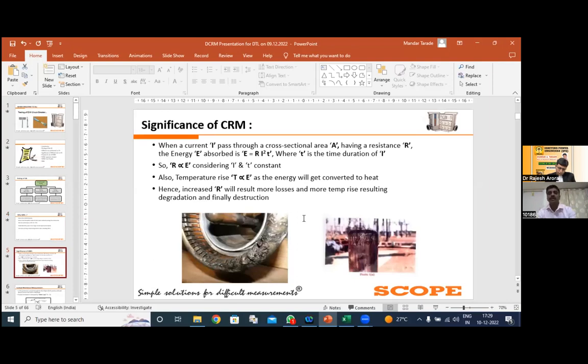Again, on my screen it is clearly visible that the increase in the contact resistance value and the temperature are directly proportional to the energy E, because E is nothing but R multiplied by I squared T. R is the resistance of the contact, I is the current passing through the contact, and T is the duration. So an increase in the R value creates more losses and more temperature rise, resulting in degradation of the contacts.